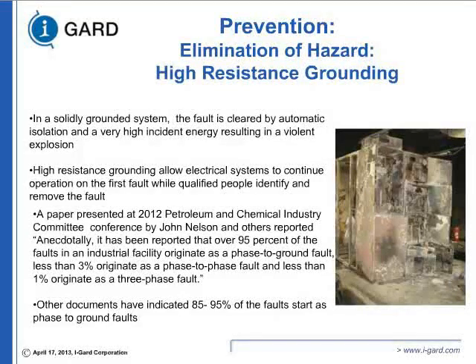Elimination of hazard: high resistance grounding. In a solid grounded system, the fault is cleared by automatic isolation and has very high incident energy, controlled by Ohm's law. With high resistance grounding, where we insert an intentional impedance in the circuit, it cuts down the energy and allows people to operate on the first fault and clear it when it's convenient or when it's possible.